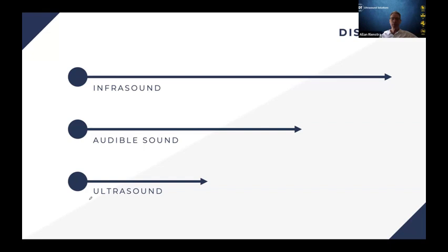Well, this is an advantage for us because we're not only trying to detect the source of ultrasound, we're trying to pinpoint its location, especially if we're looking at a substation or if we're looking at high voltage transmission and distribution lines, or if we're trying to find sources of electrical problems inside switchgear cabinets.